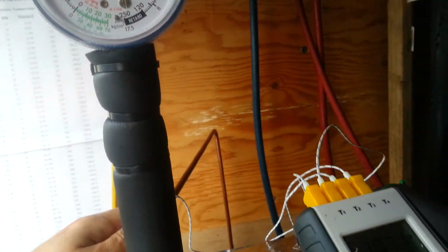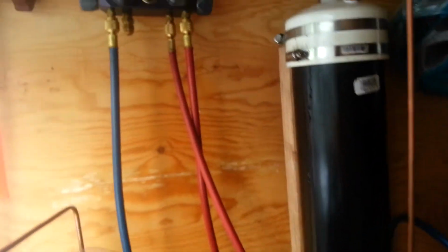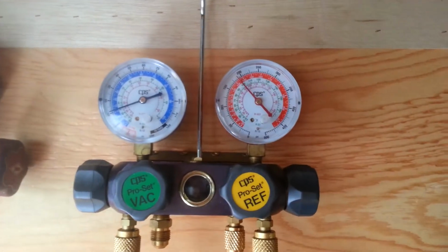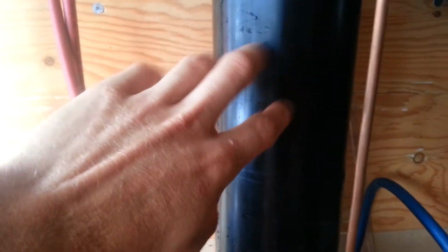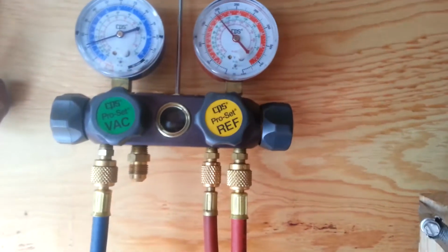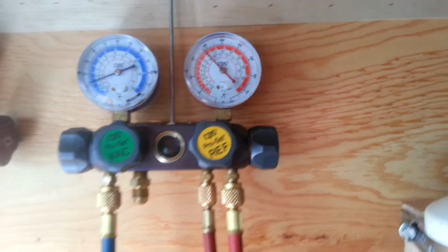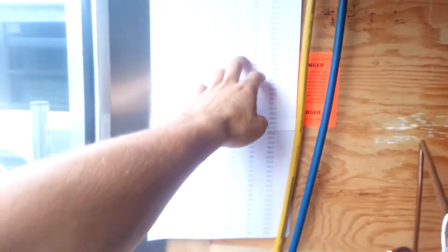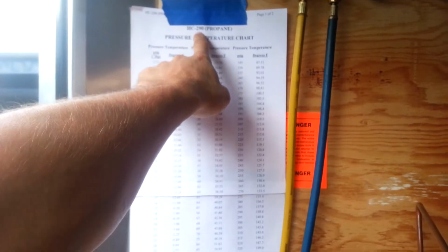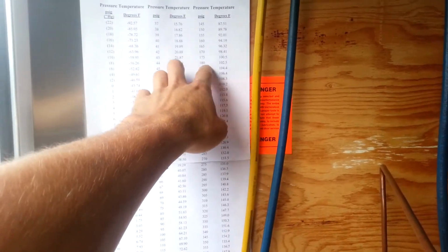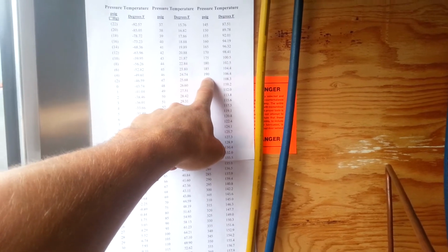So I'll let that thing even out a little bit and talk about the high side here. We're running pretty hot. This is just a water cooled heat exchanger here on the condenser. It's like 25 feet of 1/4 inch copper tubing. We're at about 180 pounds per square inch on the high side. Again, if we refer to our chart, assuming this is for R290 pure propane, what I have in this system here is actually barbecue grade. So what did I say, 190, which is 106.4 degrees Fahrenheit.